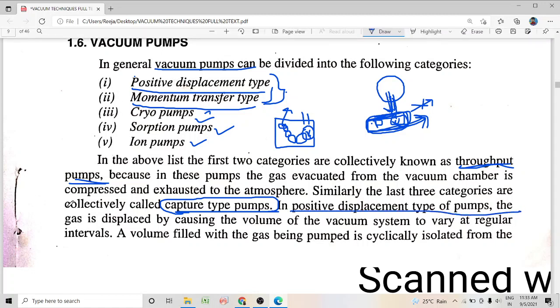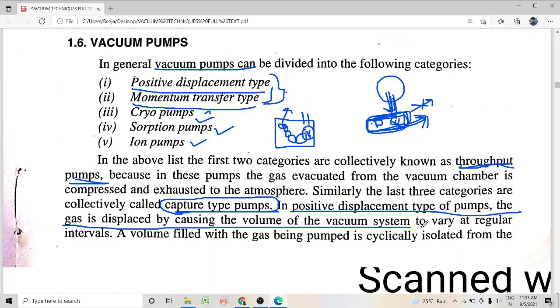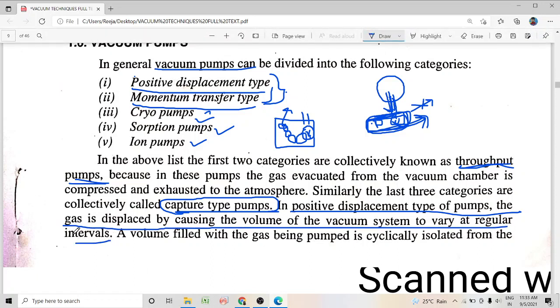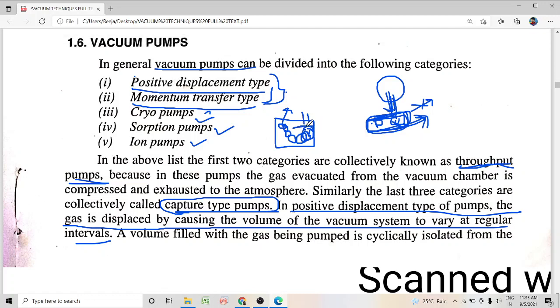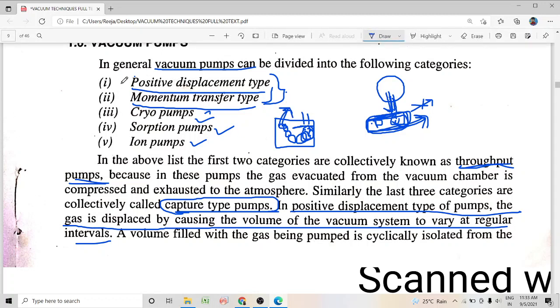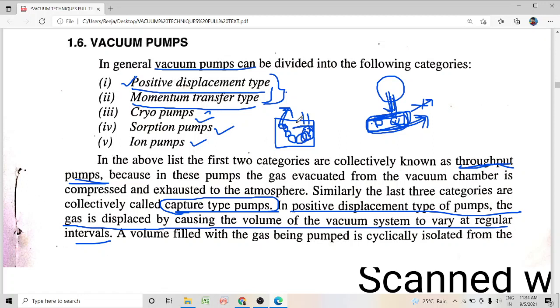In a positive displacement type of pump, the gas is displaced by causing the volume of the vacuum system to vary at regular intervals. Also, the volume of gas which is cyclically pumped out is isolated from the inlet. This volume of gas is brought to have no contact with the inlet, and then it is exhausted out of the vacuum pump. These are the features of a positive displacement type pump.